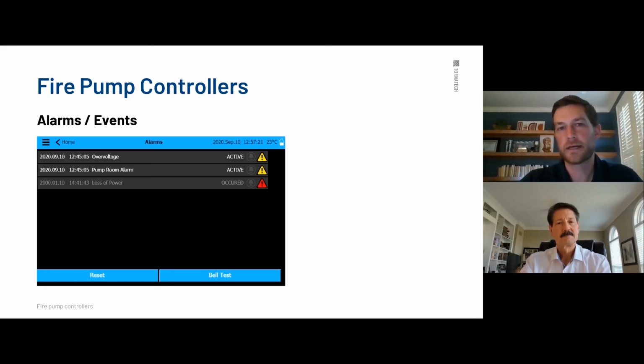Critical alarms do not clear themselves. The yellow alarms do. So if you have pump on demand, that's a yellow alarm, that kind of stuff. Over voltage, once it's corrected itself, it does go into the data. The database will always keep track of any of these kinds of alarms, but they do that automatically. With the loss of power, the critical alarms that are red, even after they've been sorted out, which this one says occurred, meaning it's not active, it is not a current problem, but it was a problem.